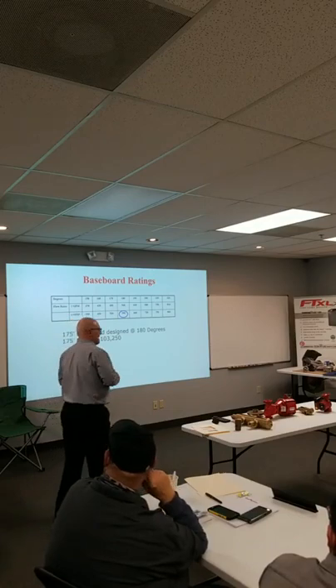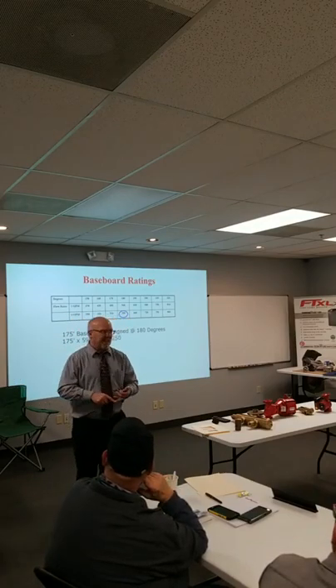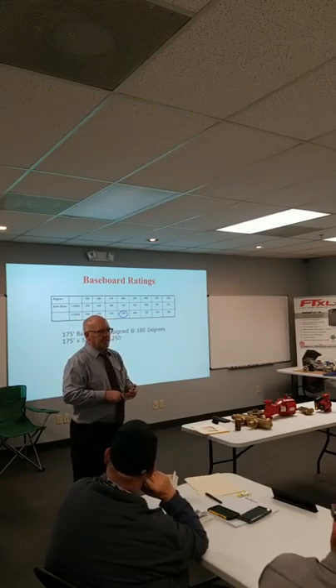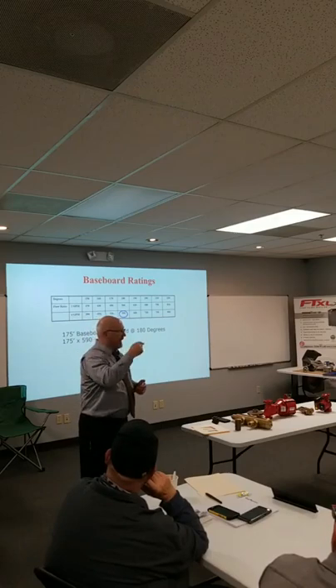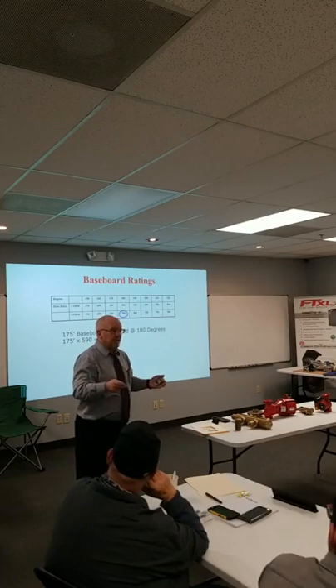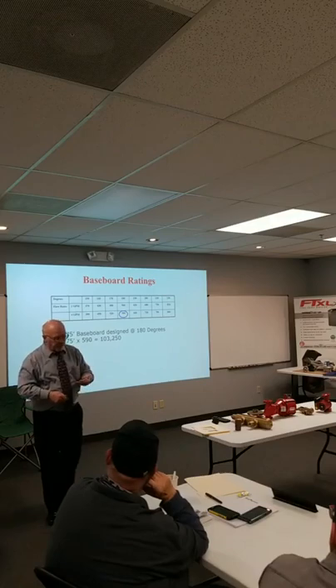Really, boilers in this area are between 50 and 200% oversized. Grossly oversized. Because people have that mentality, which I did too. A bigger boiler is going to give you more heat, right? Until I learned that, no, it doesn't. It doesn't give you any more heat.